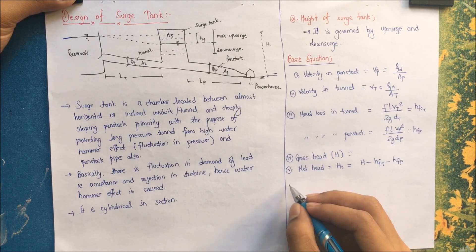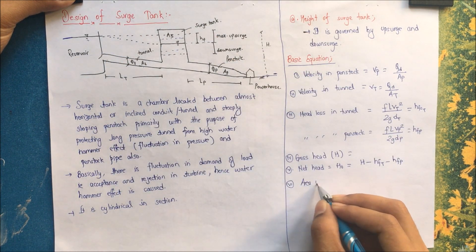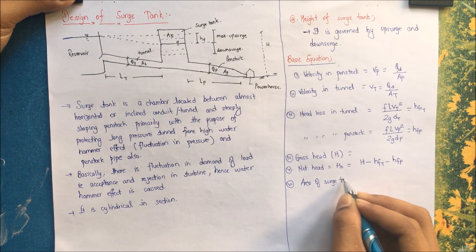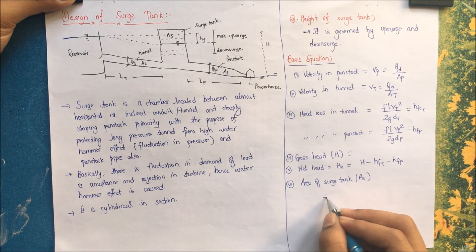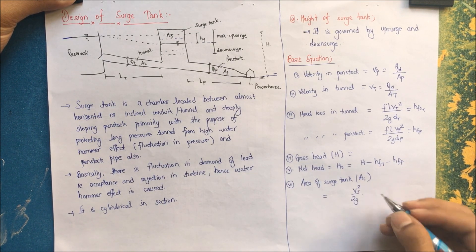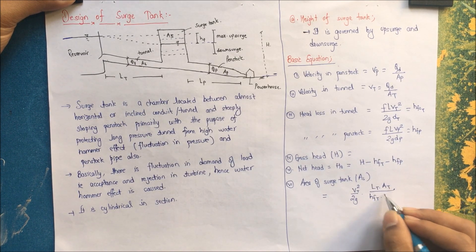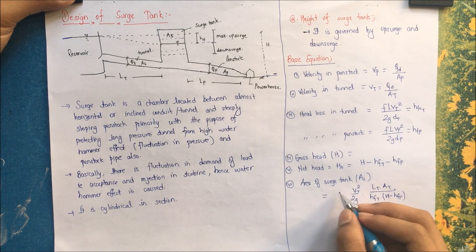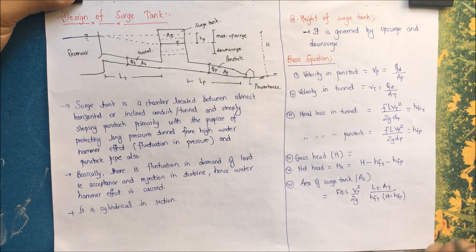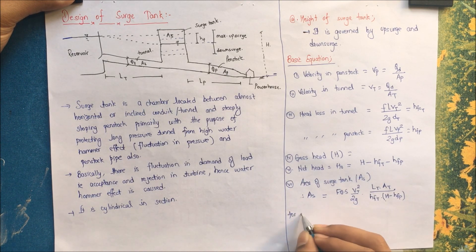Step six: the area of surge tank As = (Vt² / 2g) × (Lt × At) / (hft × (H − hfp)), multiplied by a factor of safety, giving us the required area of surge tank. For maximum surge: Zmax = Q × √(L / (At × As × g)).